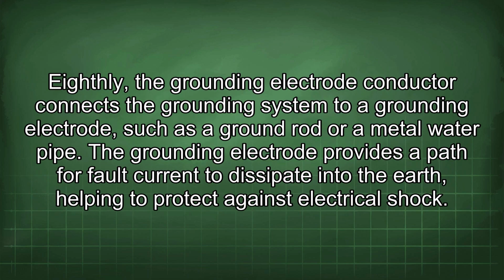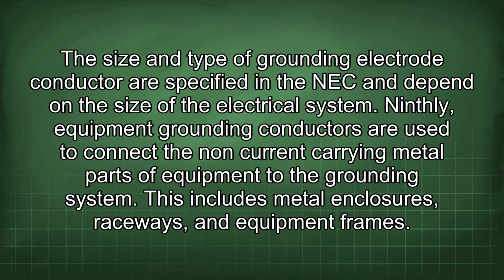Eighthly, the grounding electrode conductor connects the grounding system to a grounding electrode, such as a ground rod or a metal water pipe. The grounding electrode provides a path for fault current to dissipate into the earth, helping to protect against electrical shock. The size and type of grounding electrode conductor are specified in the NEC and depend on the size of the electrical system.